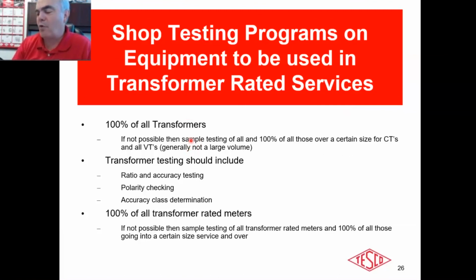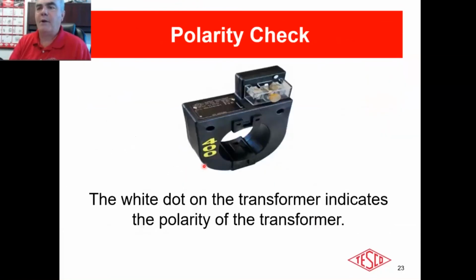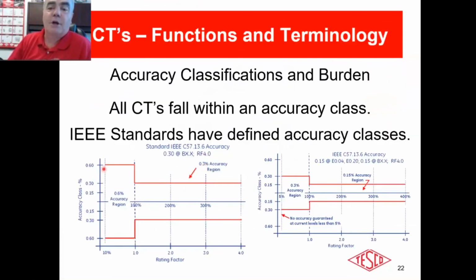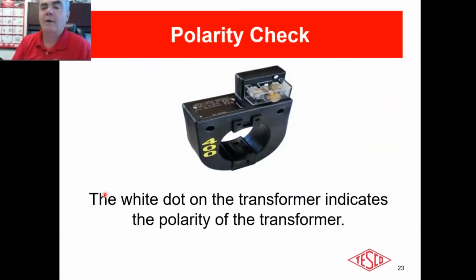What should we expect from the overall life of a CT? So the overall life of a CT is at least 30 years, and I have seen plenty that have lasted 40, 50, and 60. The real reason for changing them right now is the CTs you have out on a service may not be appropriate for that site any longer, okay? Again, the usage may have changed one way or the other. Most of them, the usage changed the wrong way. In other words, there used to be heavy usage, now there's light usage, and now I'm operating down in the 10% range, and I'm not getting much of anything, or possibly nothing, okay?